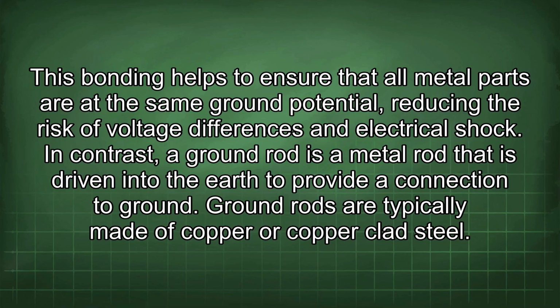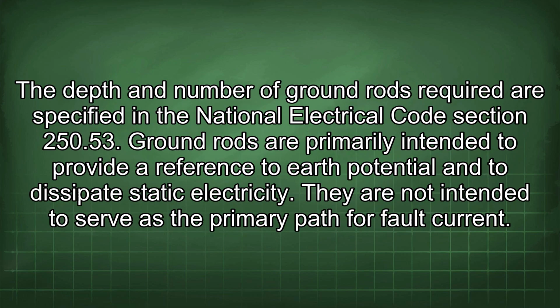In contrast, a ground rod is a metal rod that is driven into the earth to provide a connection to ground. Ground rods are typically made of copper or copper-clad steel. The depth and number of ground rods required are specified in the National Electrical Code Section 250.53. Ground rods are primarily intended to provide a reference to earth potential and to dissipate static electricity. They are not intended to serve as the primary path for fault current.